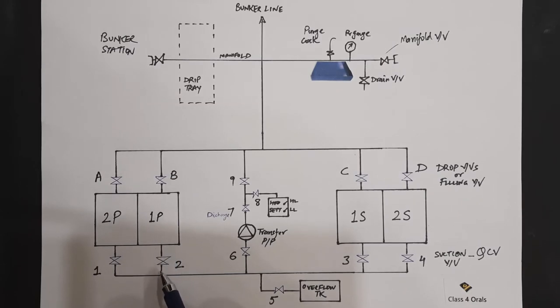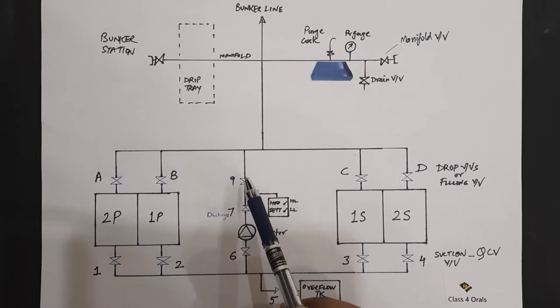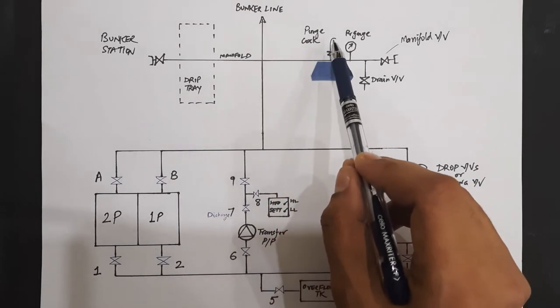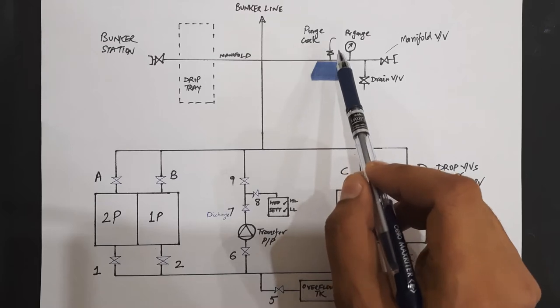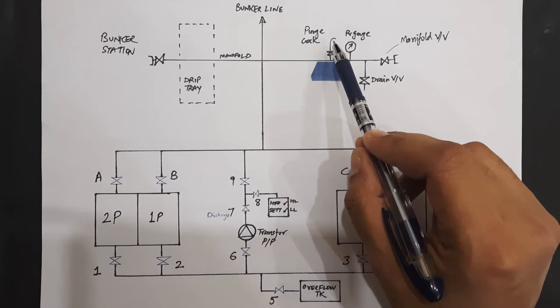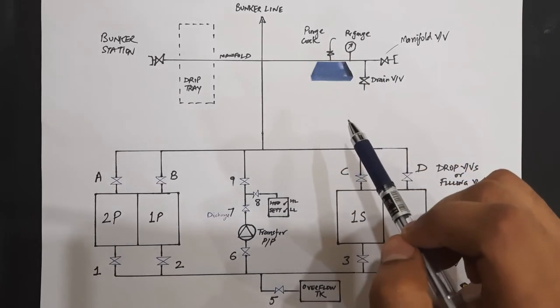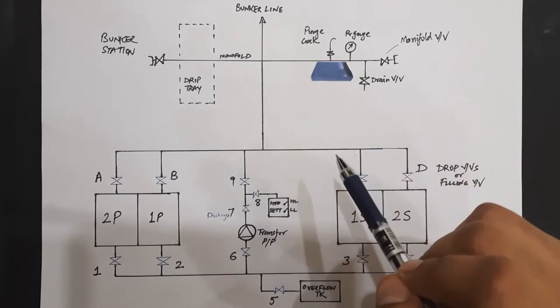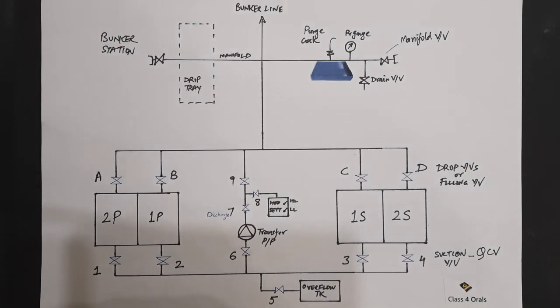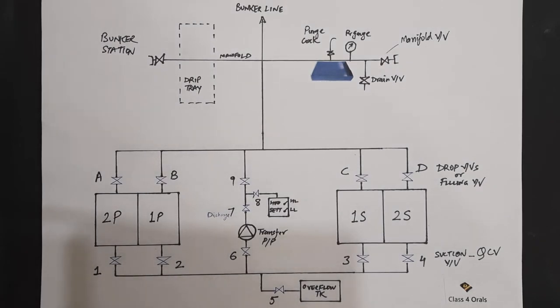So, we open the purge cock and we start the transfer pump. The oil will start going from one P to number two valve, then find its way to six, then to the transfer pump, then discharge valve number seven, nine and going to the bunker manifold. As soon as the oil is pushing the air, you can find the air will be starting coming out through this purge cock. After some time, if you can find the oil dripping from this purge cock and the oil is being collected in the tray, stop the transfer pump and also close the purge cock. This is how we have expelled out the air from the system.